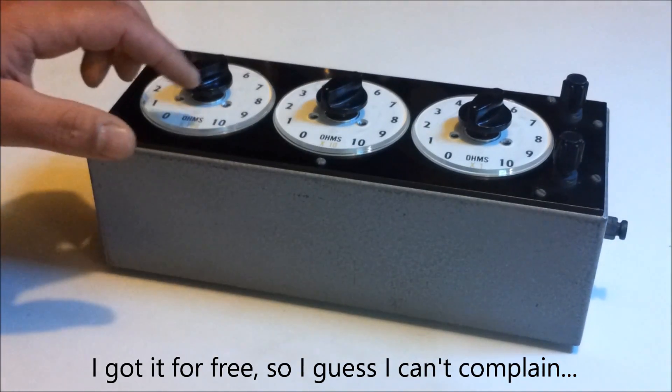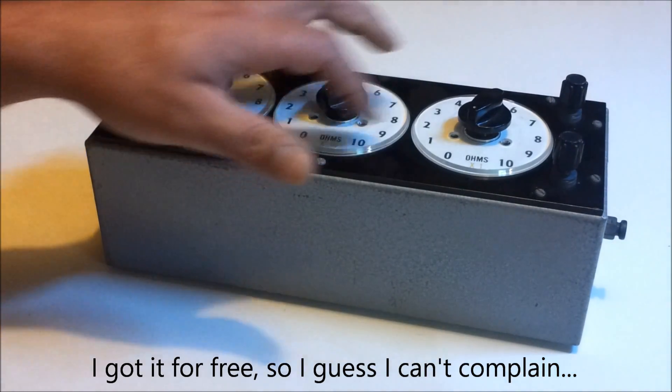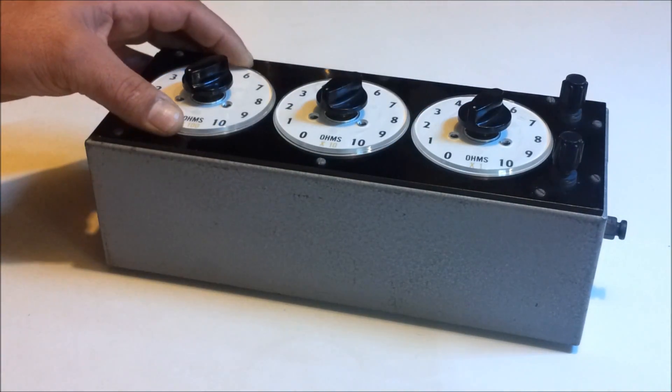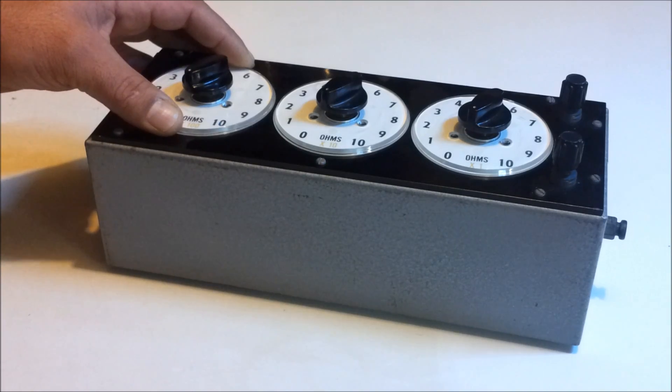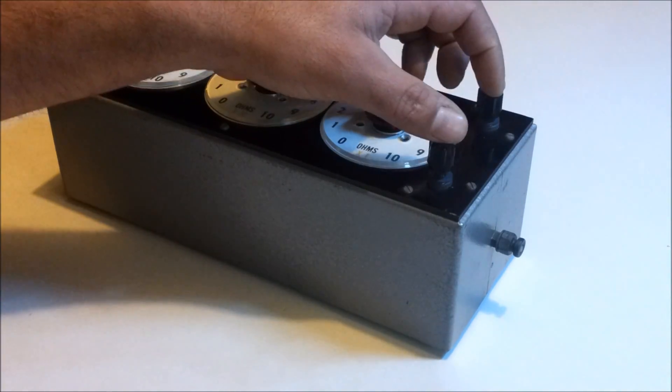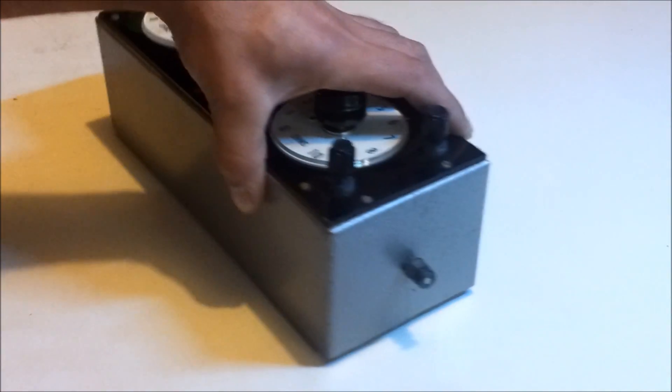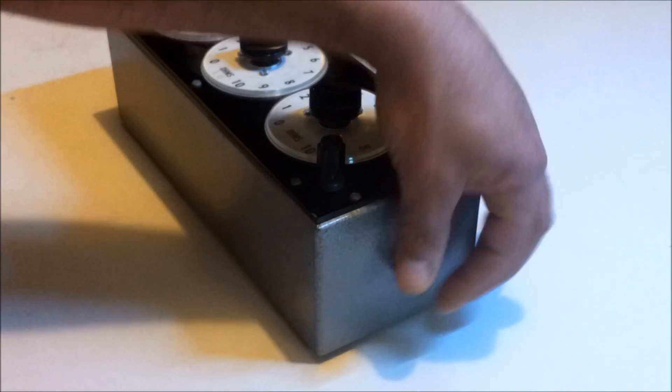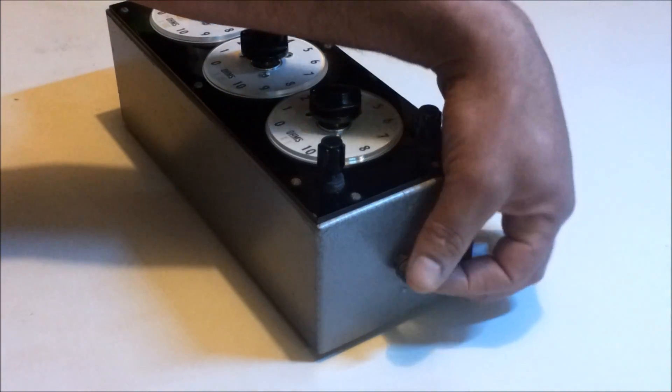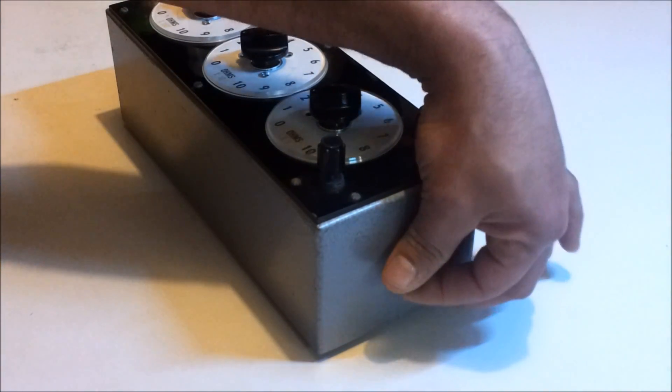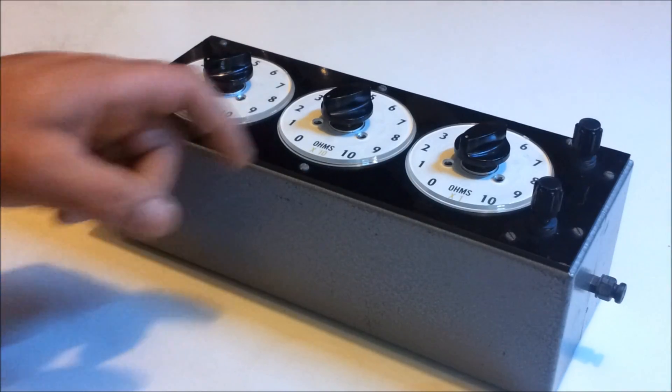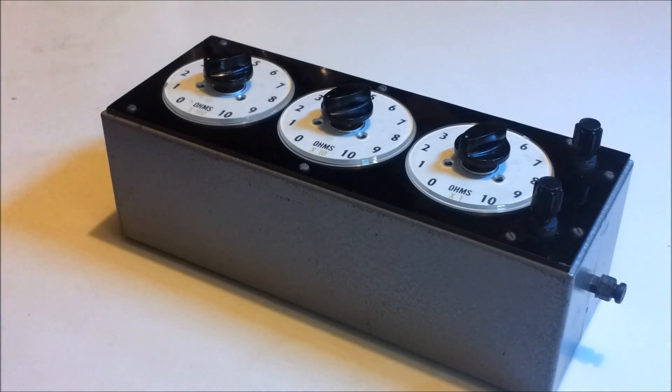This thing here will only go up to 1110 ohms or 1.110k ohms. We've got the terminals here, and on the side here you can see that there's an aluminum earth terminal for the housing here, metal housing. This top piece here is just a bit of black plastic.